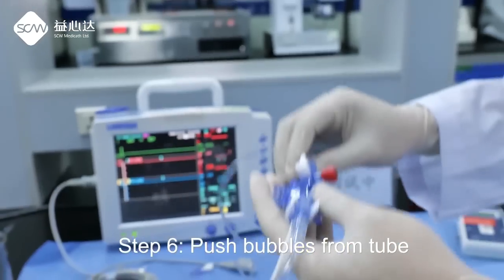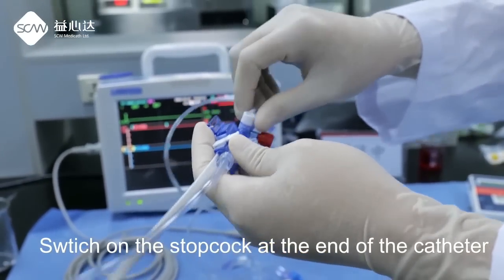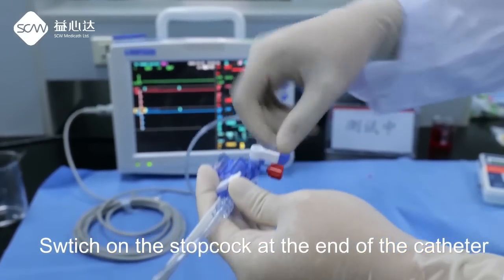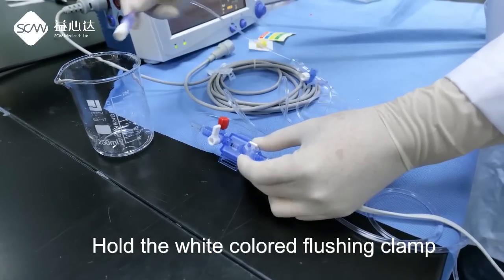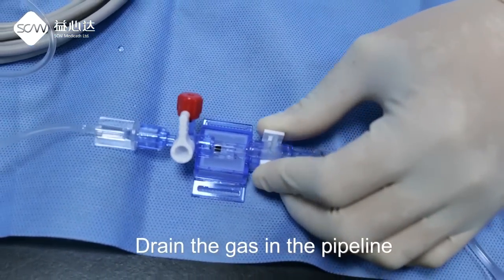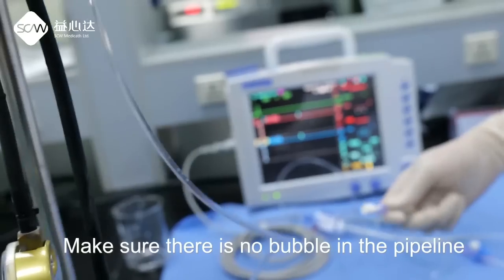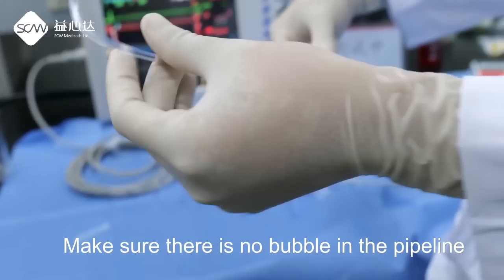Step 6: Push bubbles from the tube. Switch on the stopcock at the end of the catheter, which means the whole system is now unobstructed. Hold the white-colored flushing clamp and drain the gas in the pipeline. Make sure there are no bubbles in the pipeline.